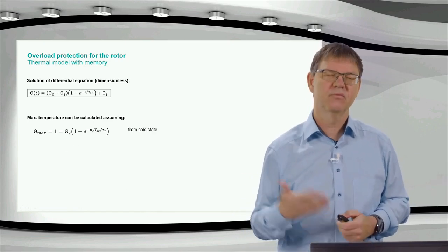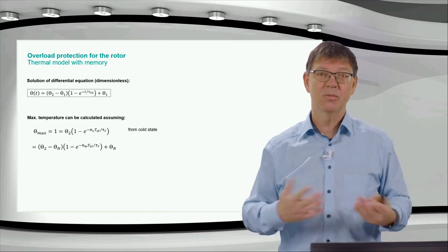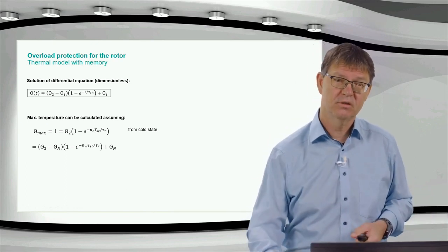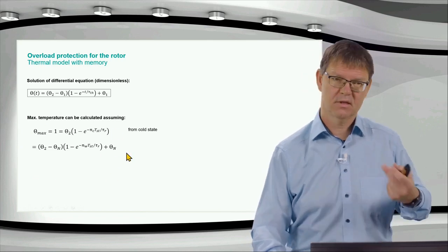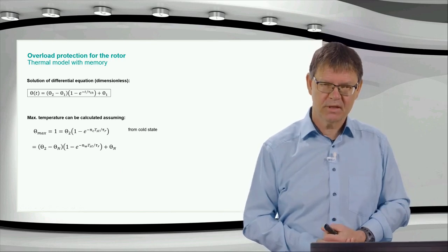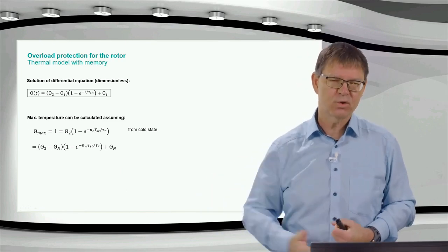This is one assumption from cold state. From warm state, it's a little bit more complex. I have n warm starts from the warm situation. And you see here now the warm state is nothing else than theta n. That means the motor is running with a nominal current, and then I have a steady state temperature situation.